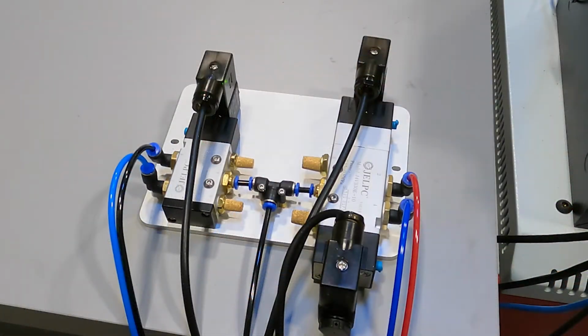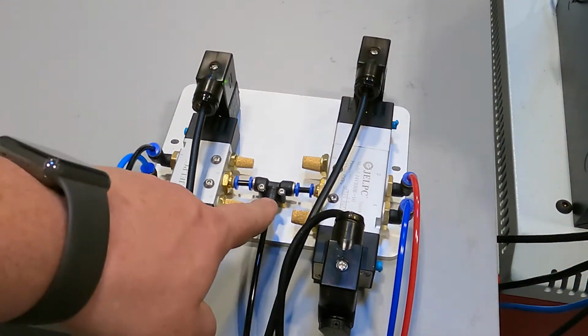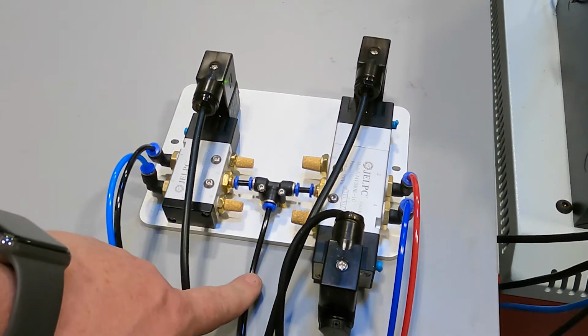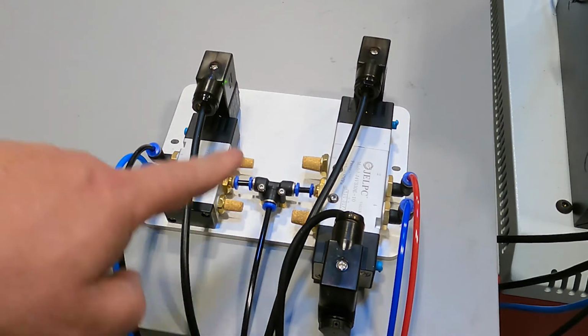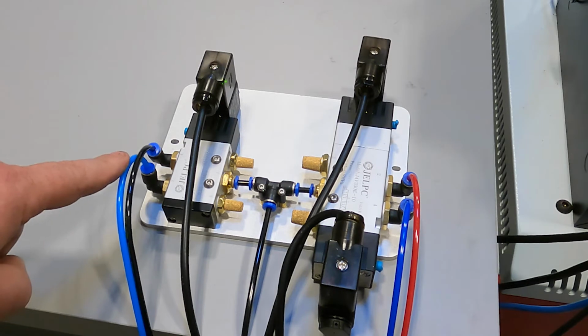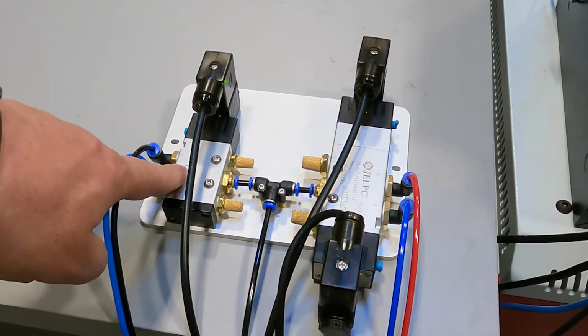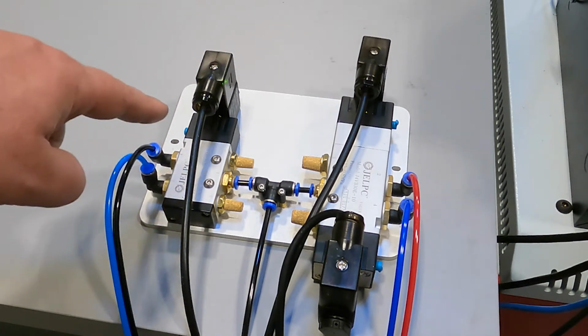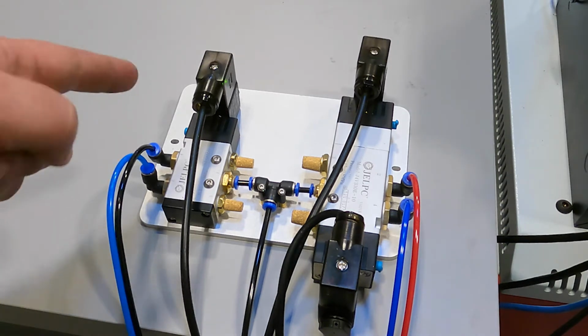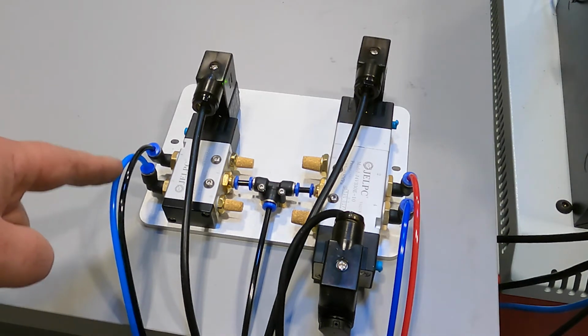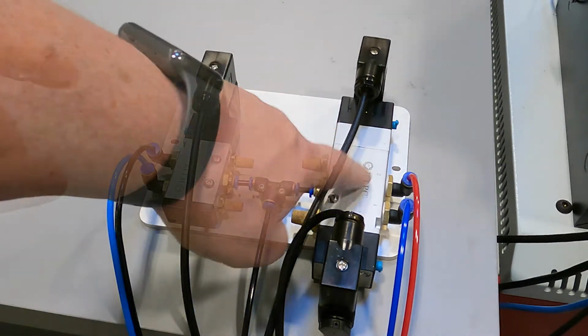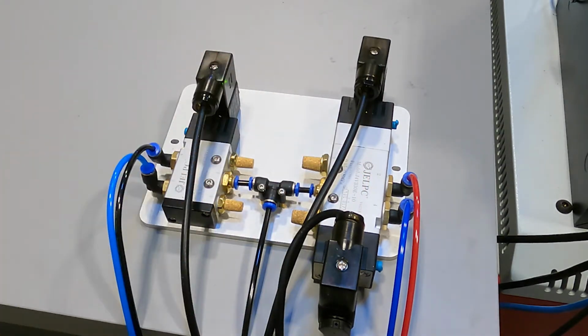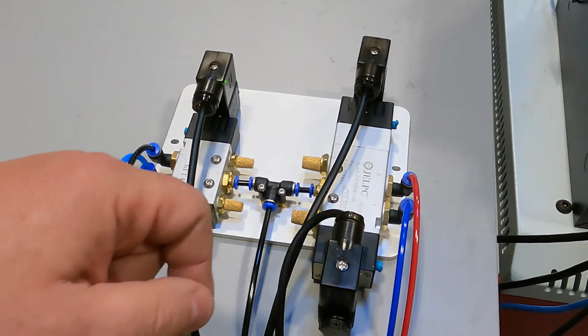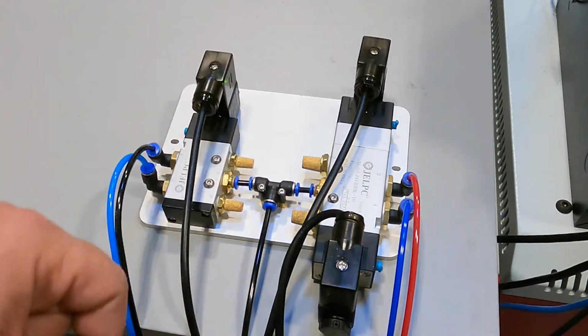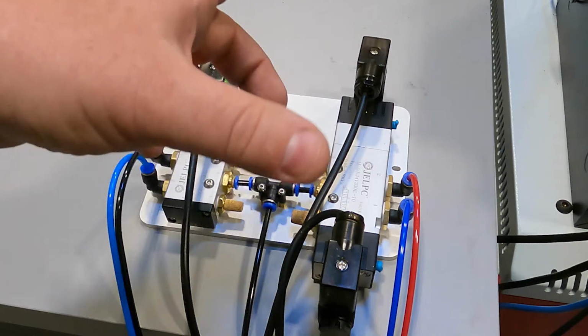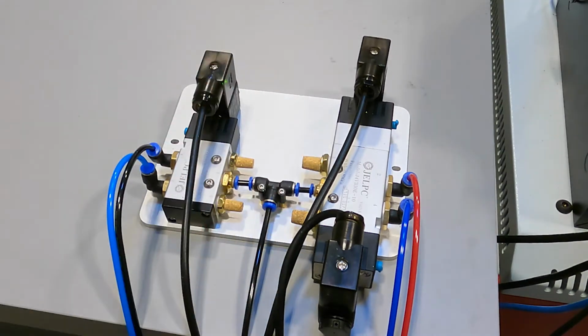Let's have a look at the pneumatics on the solenoid controller. So this is our incoming air, basically comes from our clean compressed air source. On the left-hand side, we have the control and the valve here for our vise. It's a two-state control, so basically, by convention, I set up blue to open the vise and black to close it. On the right-hand side, this controls the gripper. The gripper in this system is a three-state device, so it can be open, closed, or floating. And floating basically just means it's in neutral and there isn't pressure being applied to either side.